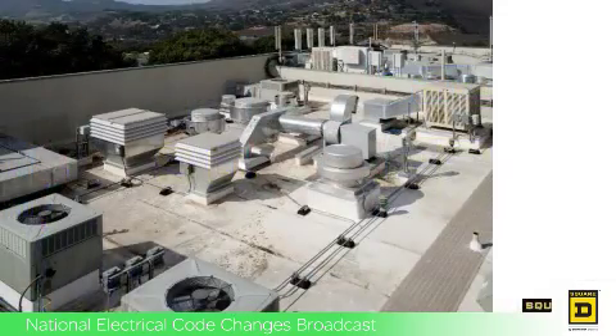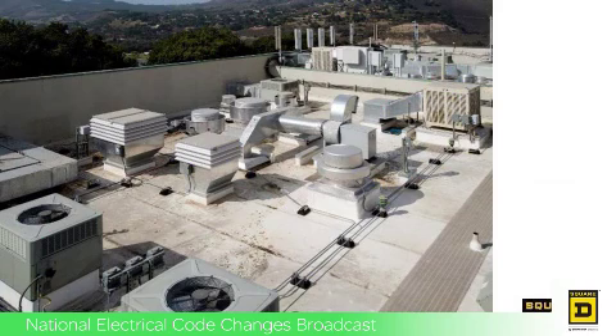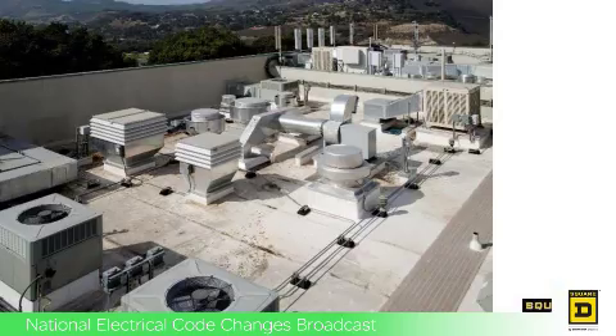So the result is that a wire type equipment grounding conductor be installed in those metallic raceway systems, and it only applies to the outdoor portions of the raceway system that are on the rooftop. And of course the wire type equipment grounding conductor would be sized based on table 250.122 at a minimum in those locations. Great. So it's pretty clear that the National Electrical Code for 2017 is full of safety enhancements for the public and electrical worker.